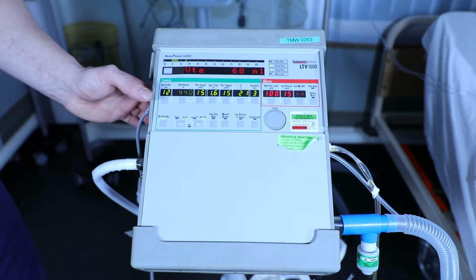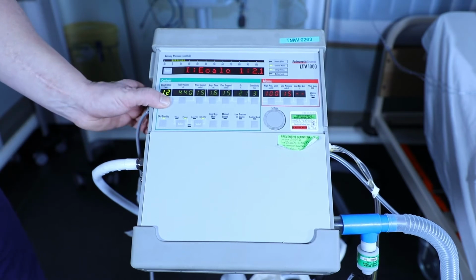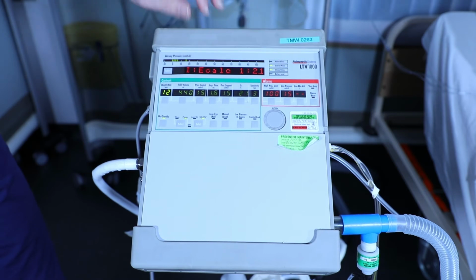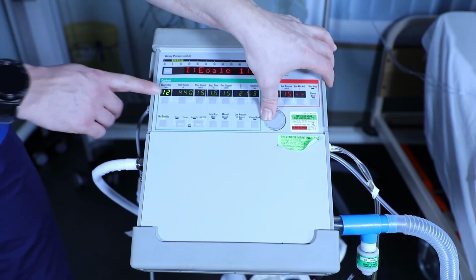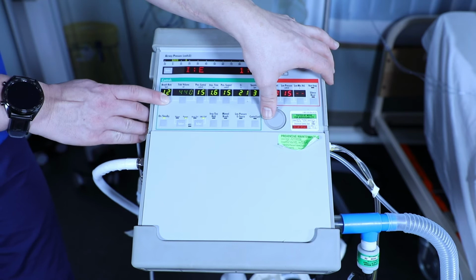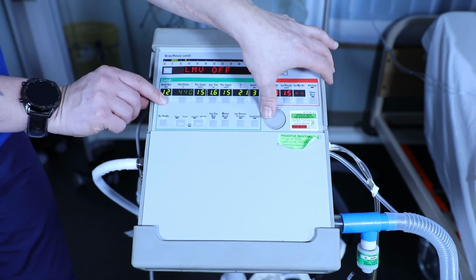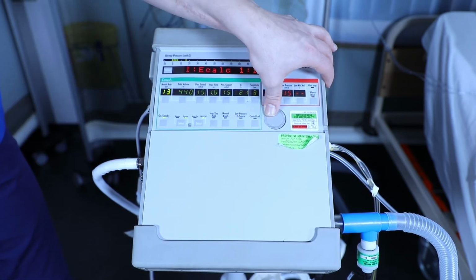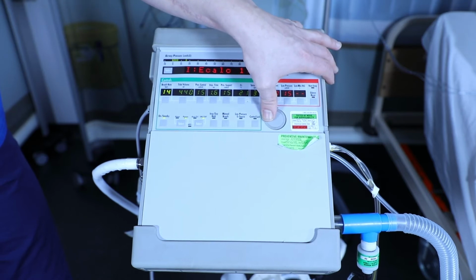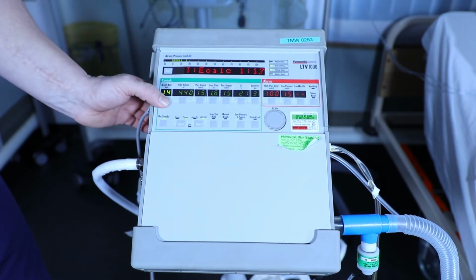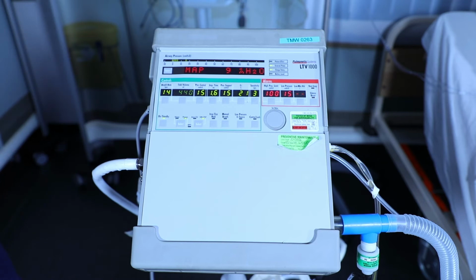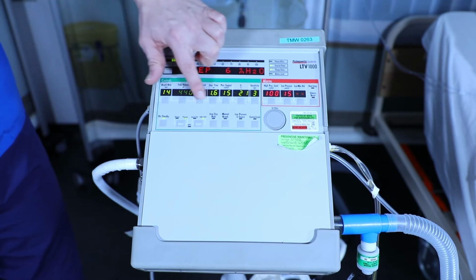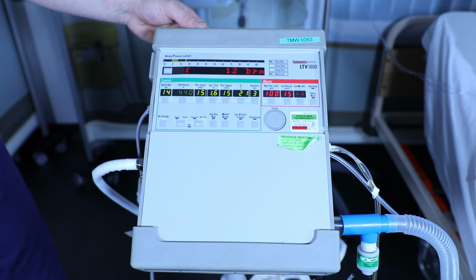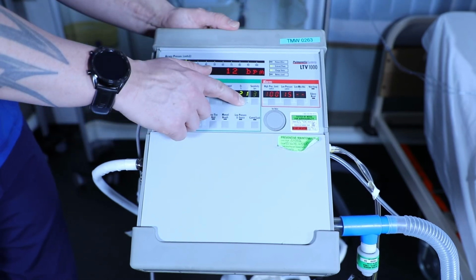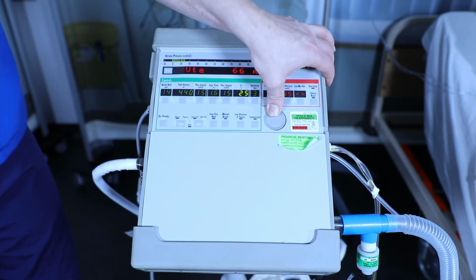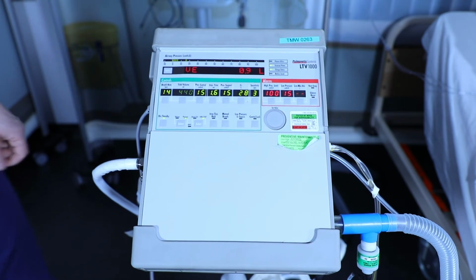To use the controls, we use breath rate for example. If we press it, we realise that the rest of the controls become dimmed to tell us that we are now on this. We have a few seconds before this will cancel, so again, press the breath rate, use the jog dial to go up and down and select the appropriate setting. Press the button again to confirm, and this goes for the remainder of the buttons. So just another example: to increase the oxygen, press the oxygen and switch the oxygen up, press to confirm.